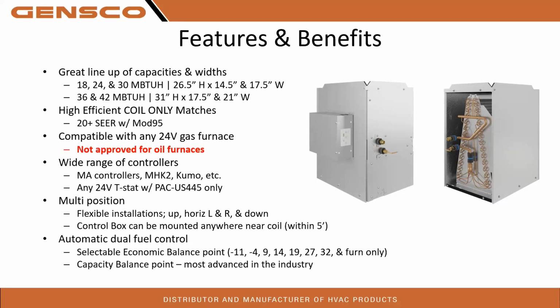Our coils are coil-only matchups with Mod 95 furnaces and some of those higher efficiency furnaces. We've seen SEERs over 20, which is pretty darn good for a coil-only matchup. Again, compatible with 24-volt gas furnaces, not approved for oil furnaces. That's important to know. Oil furnaces burn a little bit too hot for these, not tested, not approved for use on those. So make sure you stick with gas or propane only.